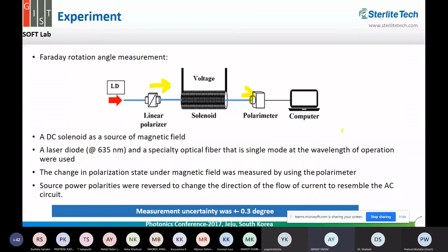So what do we do there? I will show one example here, of how we sense the magnetic field instead of using a conventional current transformer. We take a laser diode and this optical fiber here, and we have to take care that linear polarization goes in, because as you know the polarization is otherwise very random. So we make linearly polarized light pass through this optical fiber. We create a magnetic field using a solenoid, and there is a polarimeter which tells how much the rotation of your polarization is, which can be determined automatically by computer software. So we pass that light, and when the magnetic field is generated, there is a change of rotation. Okay, so this is what we get.